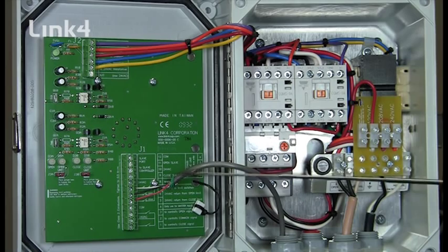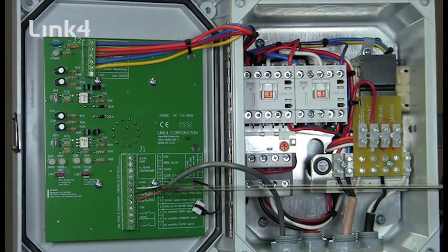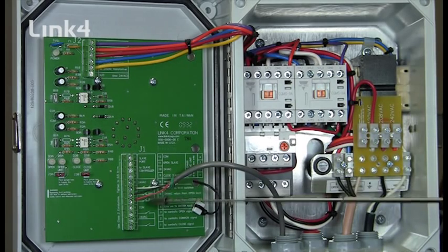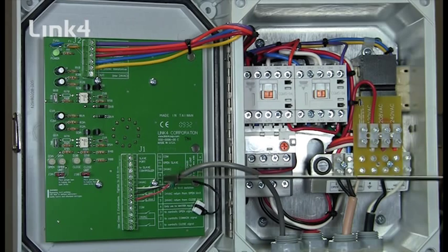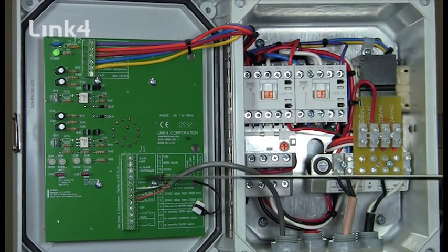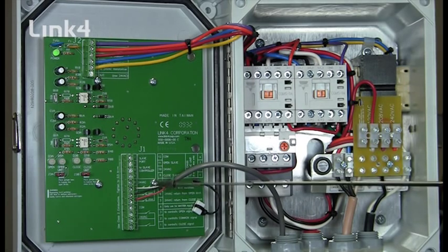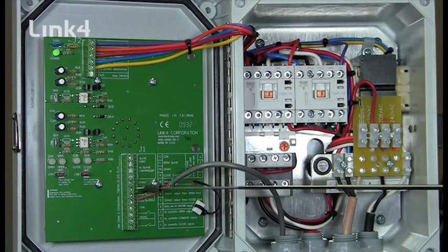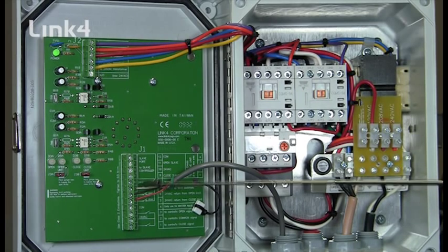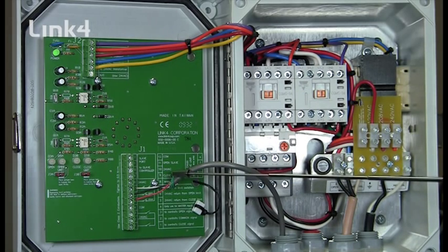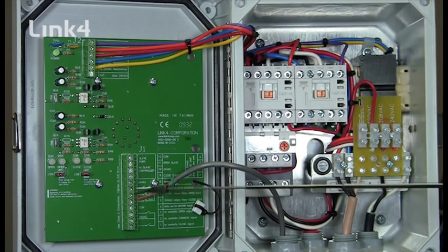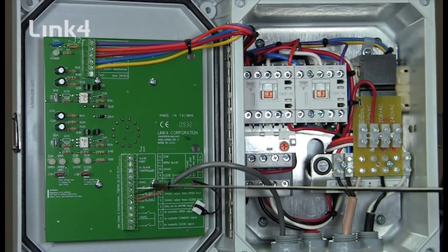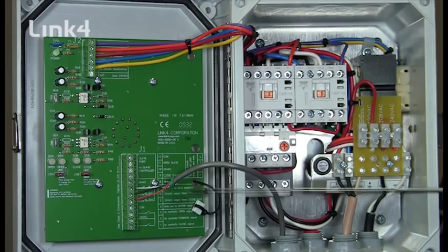Over for the limit connections we have a 3 wire connection. We have a white, a black and a red wire. The white wire is going through, from the iDrive 300 it will go through both secondary limit connections. The black wire is for our open and the red wire is for our closed limit.